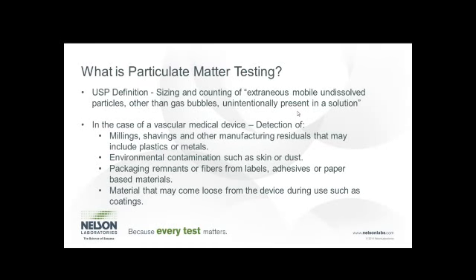What is particulate matter testing? USP 788 defines particulate matter testing as sizing and counting of extraneous mobile undissolved particles other than gas bubbles that are unintentionally present in a solution. This is in regards only to a solution since the USP does not deal with medical device particulate matter content. However, in this case, we would probably substitute that solution with device.